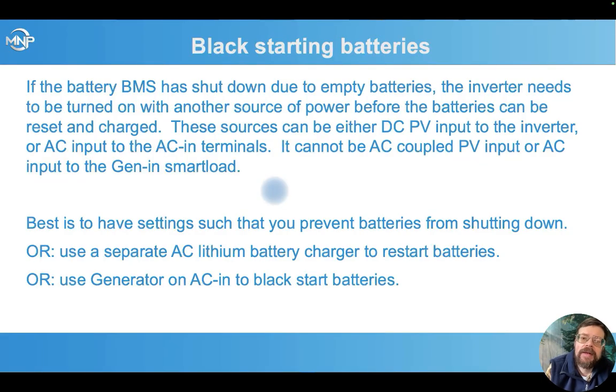So, what do you do about black starting your batteries? Using your DC PV input is one way, but if you manage to get in a situation where you shut down, probably it's because you didn't have much solar resource at the time. Best is to have your settings such that you shut the inverter down before the battery shut down and don't end up in this situation, but it can still happen.